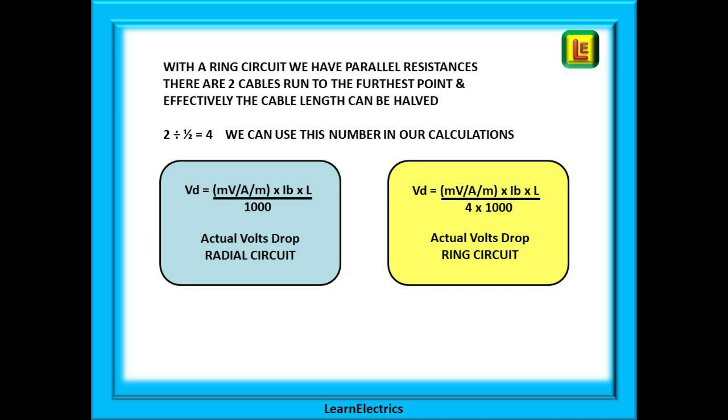We've shown on this slide the two standard formulas for voltage drop calculations. On the left in the blue box is the formula for radial circuits which you should be familiar with. On the right in the yellow box we show the formula for ring circuits, and you can see the number four that we've just worked out on the bottom row of this formula. If you remember from R1 plus R2 calculations, we also divide by four for ring circuits.